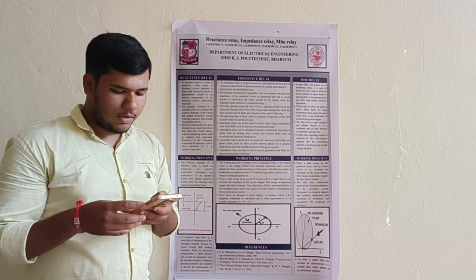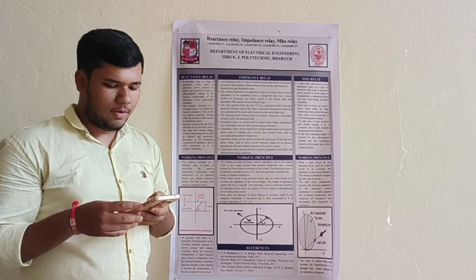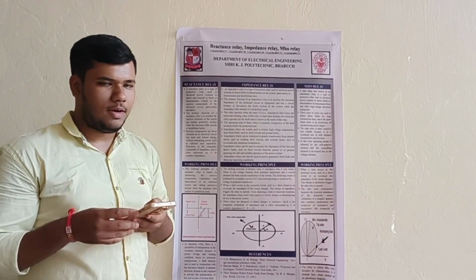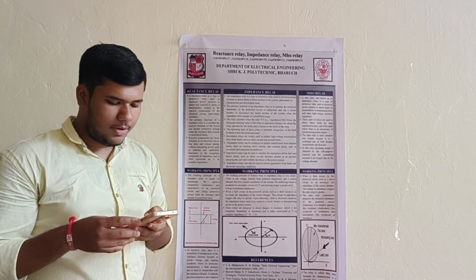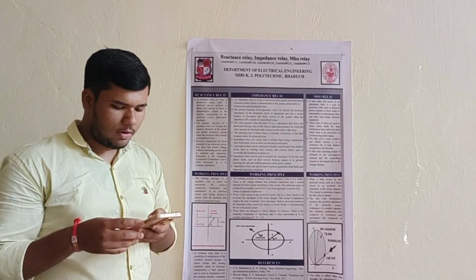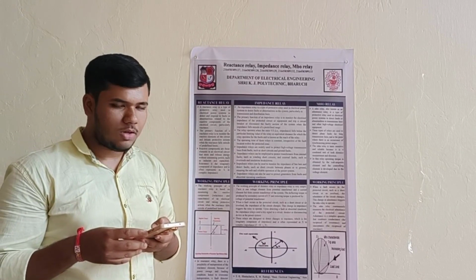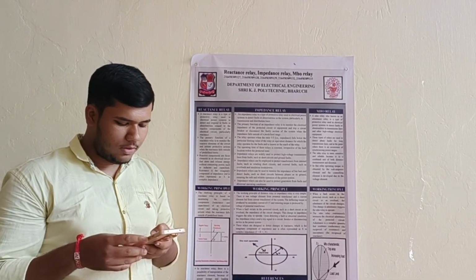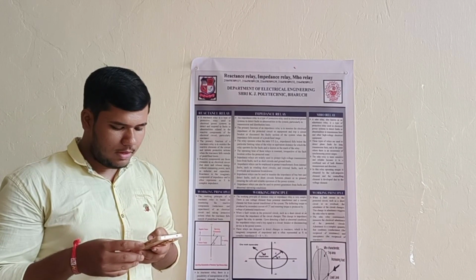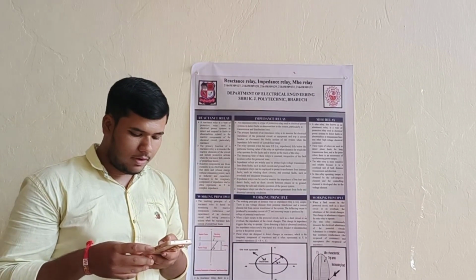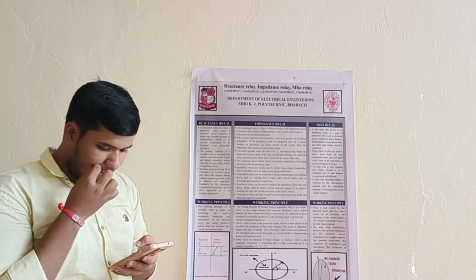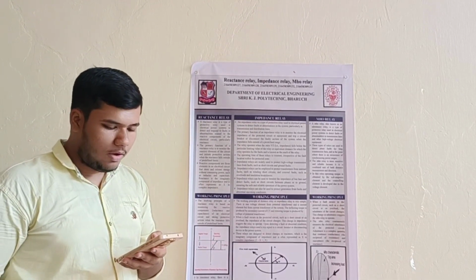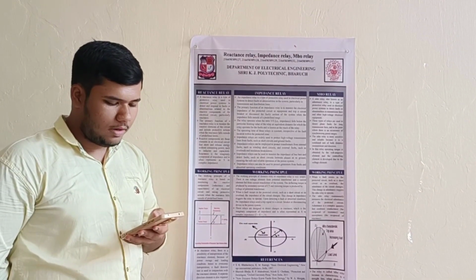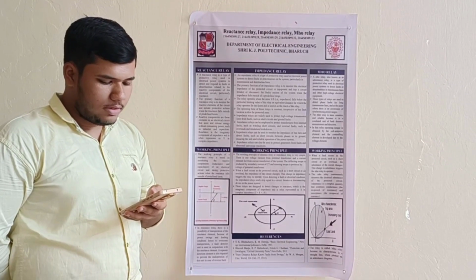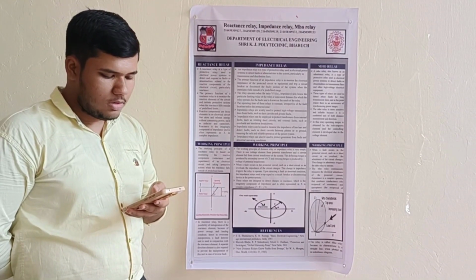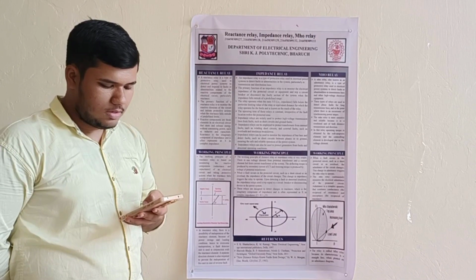The voltage is derived from the potential transformer and the current is derived from the current transformer to determine the impedance. Now two essential torques play a critical part in the relay's operation. One is the deflecting torque while the other is the restoring torque. The importance of these two torques for relay functioning cannot be overstated. The deflecting torque is generated by the secondary current of the current transformer. The restoring torque is provided by the voltage of the potential transformer.